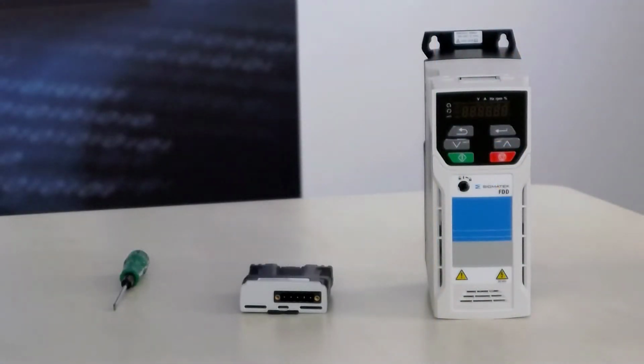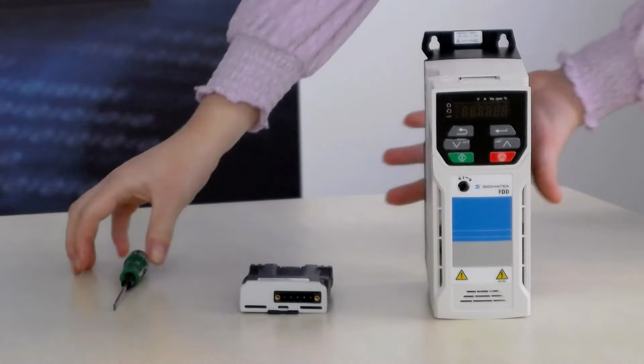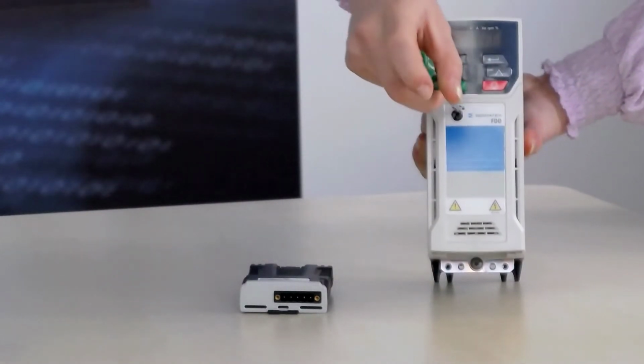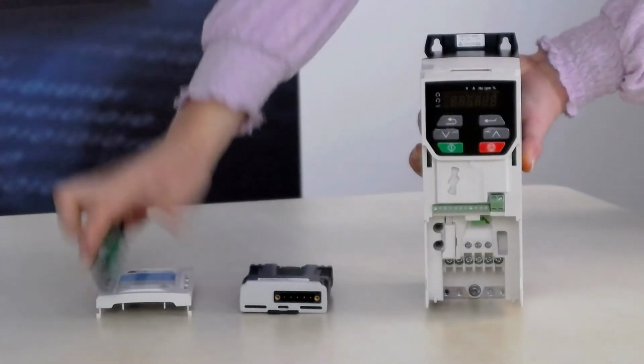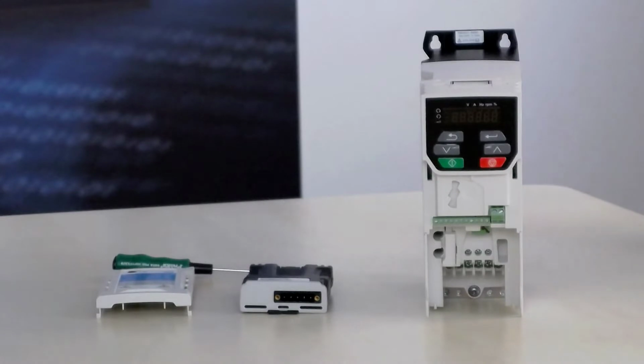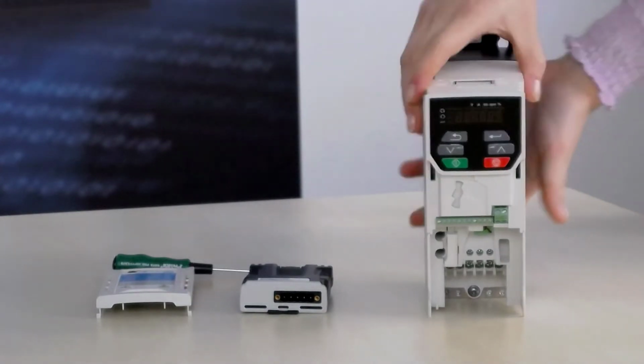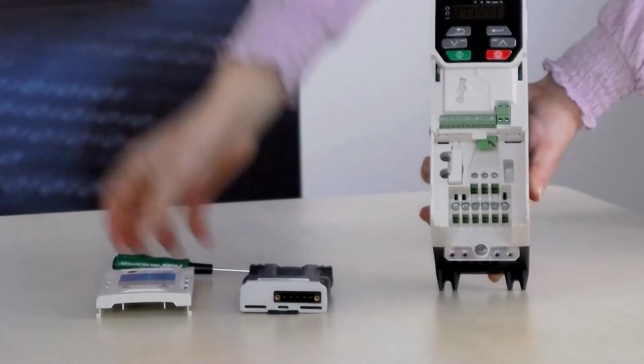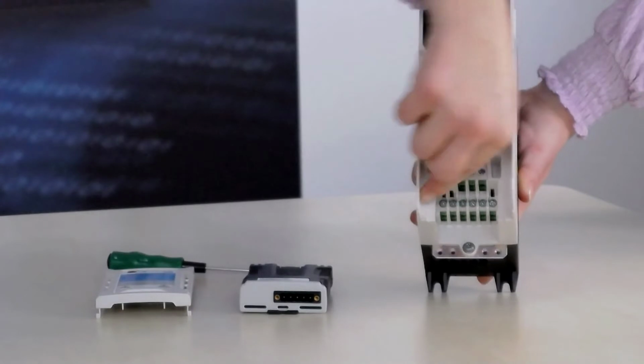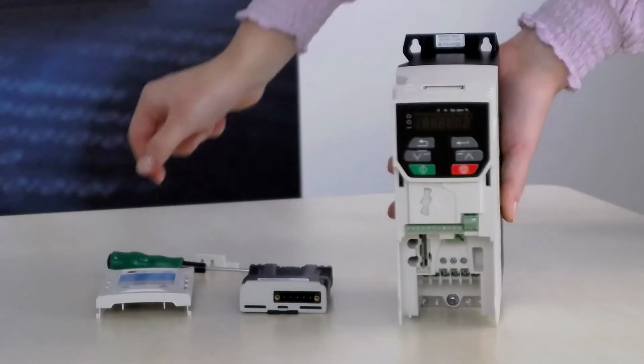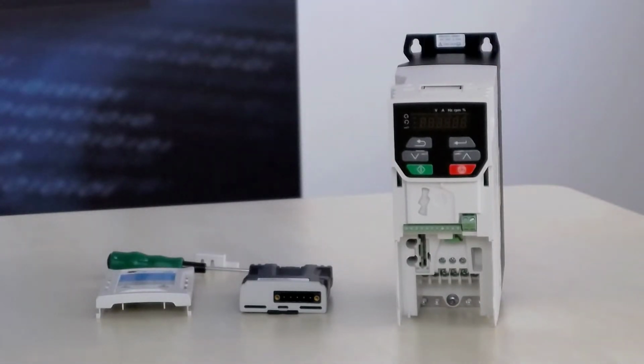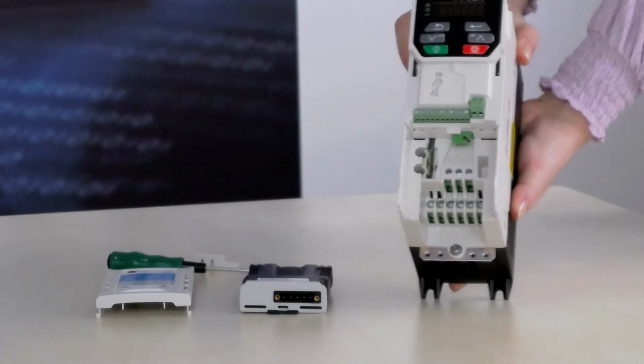At first, I want to show you how to set up the interface modules. All you need is a screwdriver. Take the FDD3000 and the screwdriver and turn the lock to open the lid. Next step is to remove the little protector. Therefore, you take the screwdriver and carefully unattach the protector. After this, you can clip in the interface module.